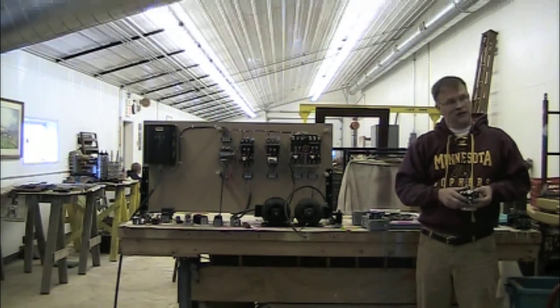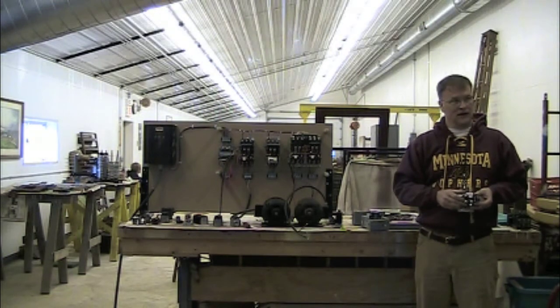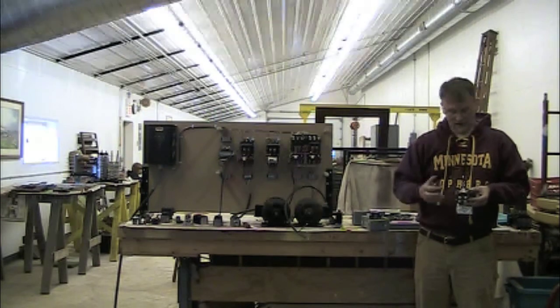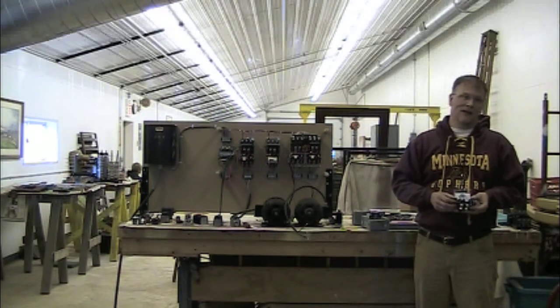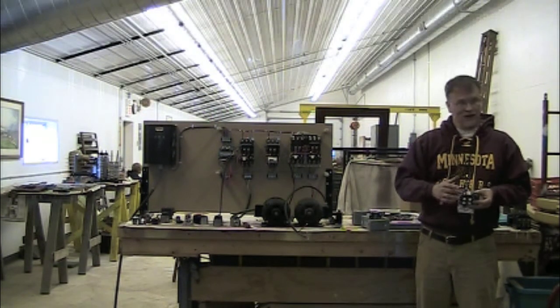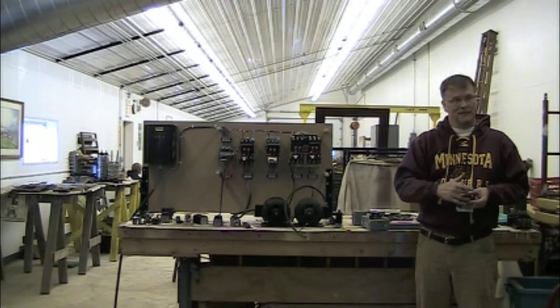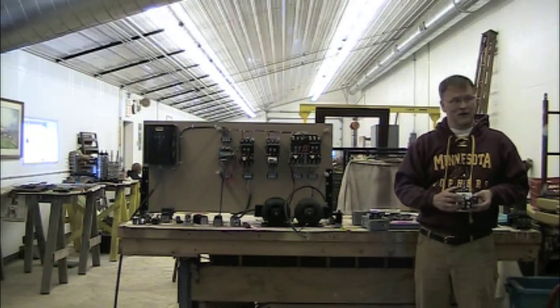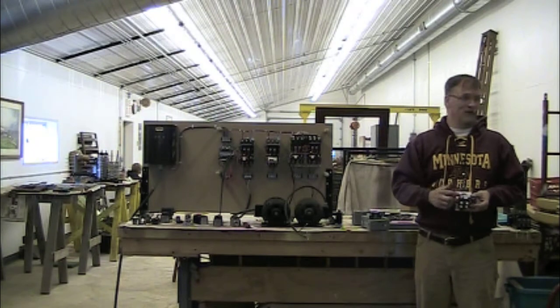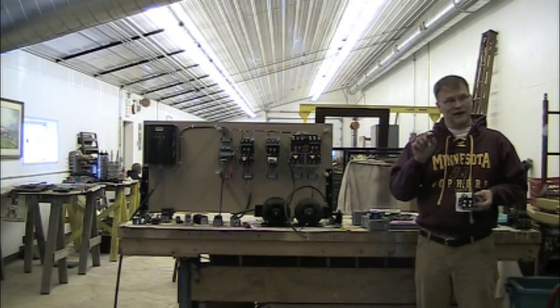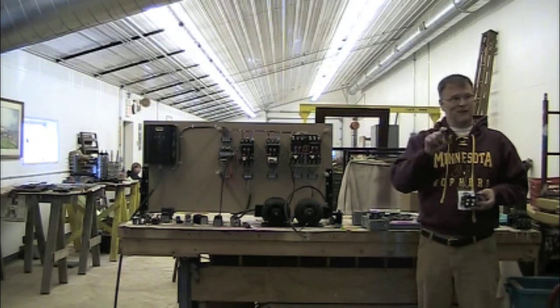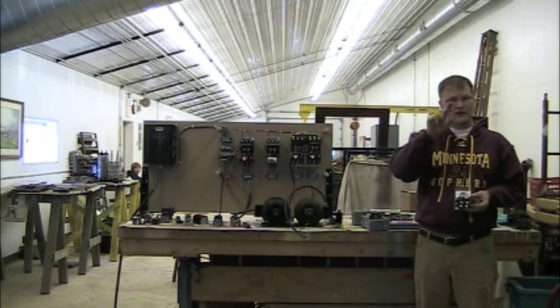So the scenario where you want to run a single phase motor off of it, say you're running a 240 single phase, the way that you need to do it on the Allen Bradley side is you have to have all three of them populated to have continuity, but you also have to have current going through all of them. So if you look at their single phase wiring, they wire up through one, back through the other, and down. So it's really confusing looking.